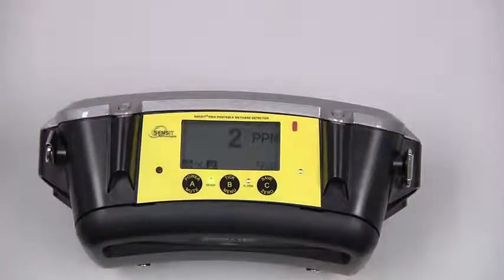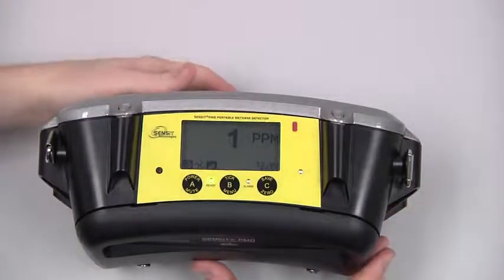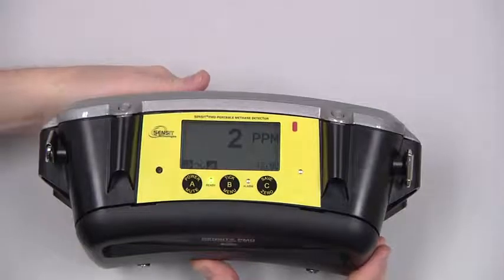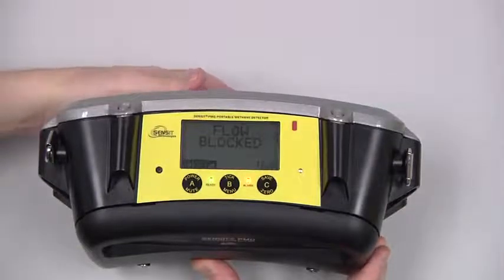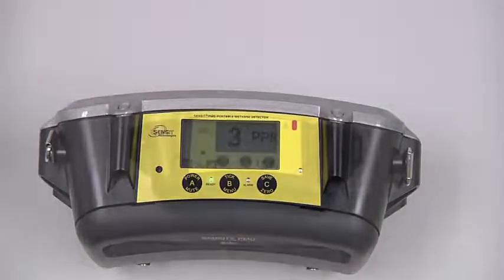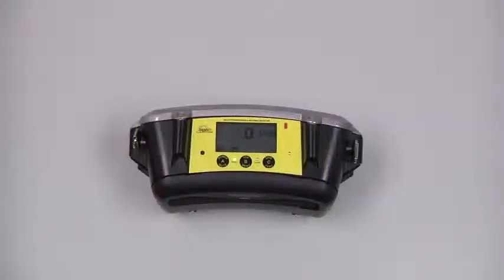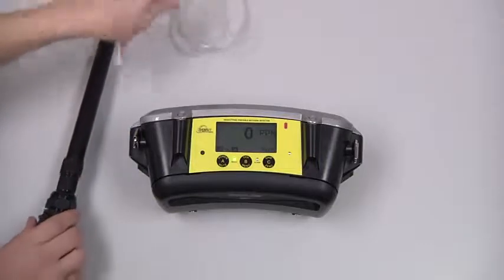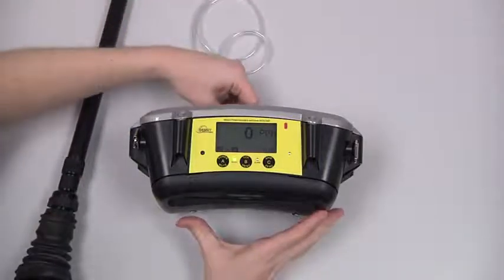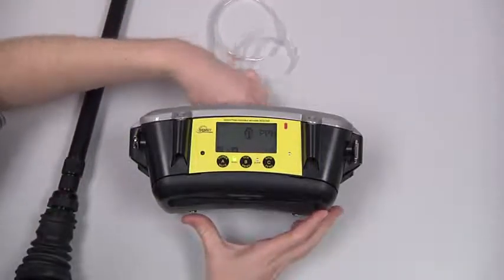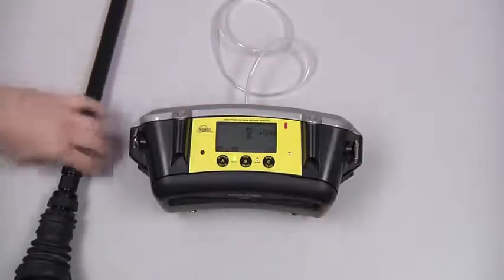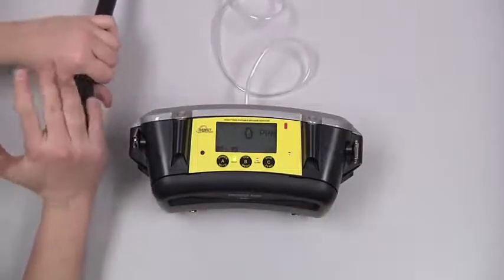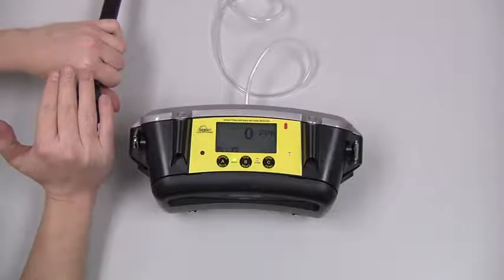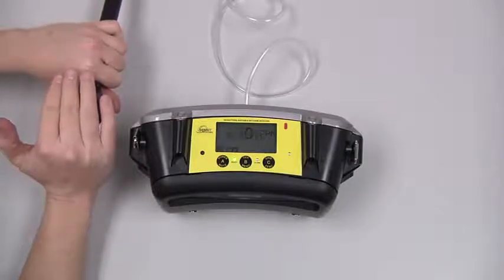We then need to do a flow block check. We can do that by blocking the inlet with the finger until the instrument shows flow blocked. If we're going to use an attachment such as the survey probe, we'll need to do a flow block check with that attached. So we can attach the probe to the instrument and block the intake, ensuring that the instrument shows flow blocked.